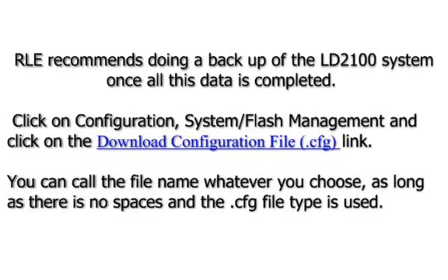RLE recommends doing a backup of the LD2100 system once all this data is completed. Click on Configuration, System Flash Management, and click on the Download Configuration File .cfg link located on the page. You can name the file whatever you choose, as long as there are no spaces and the .cfg file type is used.